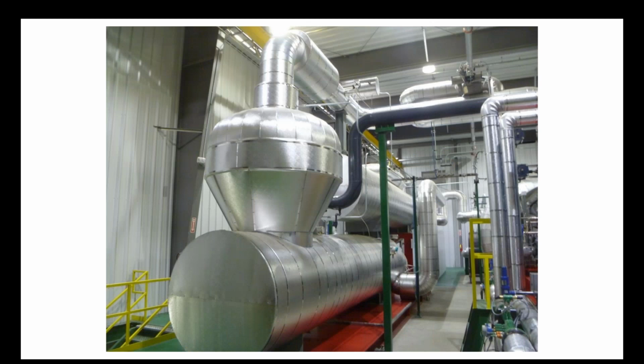And we installed the 2.2 megawatt CHP model. Seen here are the preheater and the evaporator. The closed loop silicone-based operating fluid is circulated using pumps in the basement. The fluid passes first through the regenerator, then to the preheater and evaporator shown here, where a series of coils circulating 280 degree thermal oil converts it to vapor. Next slide, please.